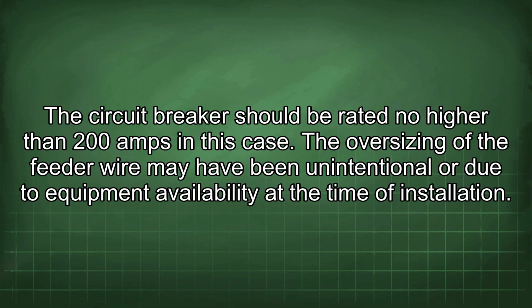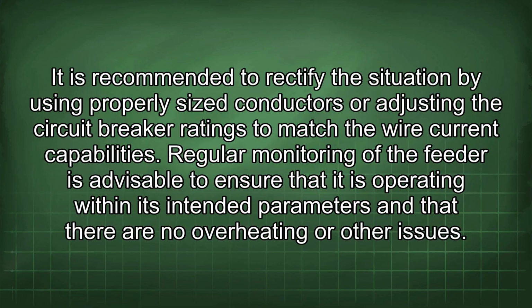The oversizing of the feeder wire may have been unintentional or due to equipment availability at the time of installation. It is recommended to rectify the situation by using properly sized conductors or adjusting the circuit breaker ratings to match the wire current capabilities. Regular monitoring of the feeder is advisable to ensure that it is operating within its intended parameters and that there are no overheating or other issues.